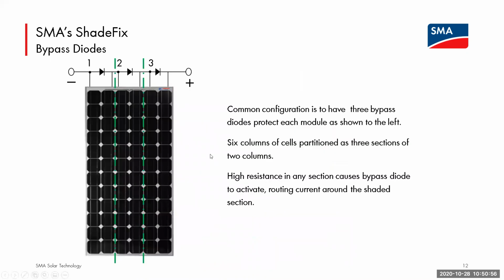So here's another way to look at it. Here we see a visual of a traditional solar panel or solar module. You have your cells, and typically you have 3 bypass diodes. Each diode allows it to act as a traffic cop or pressure relief valve for a third of the module. So we have the left third, the middle third, and the right third of the module. If any section of this first third is shaded, that bypass diode will allow current to bypass or jump over that shaded section and flow through sections 2 and 3. And this is really how SMA ShadeFix algorithm works in tandem with the modules you've installed to pull the most power off of the non-shaded sections.